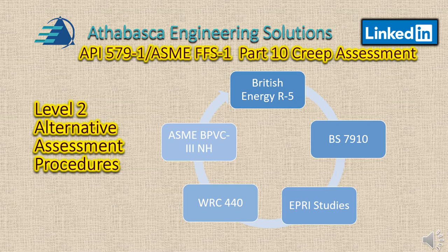There are other methods besides API 579 to assess these procedures, and they've been developed quite extensively over the last 20 years, especially for serious problems associated with CREEP and cracking. The British have a standard called R5. There is another standard called BS 7910.